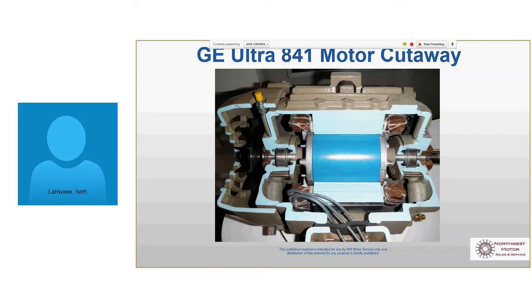So it's just not ideal. For GE, that number is about 75 horsepower. Above that, what they like to do in shaft up or down applications is they actually redo the grease path so that we're not feeding grease in from this side, we're feeding grease in from this side. Say it's shaft down, so this is going to be the down side. We want the path to come in from the high side of the bearing and purge out through the low side.